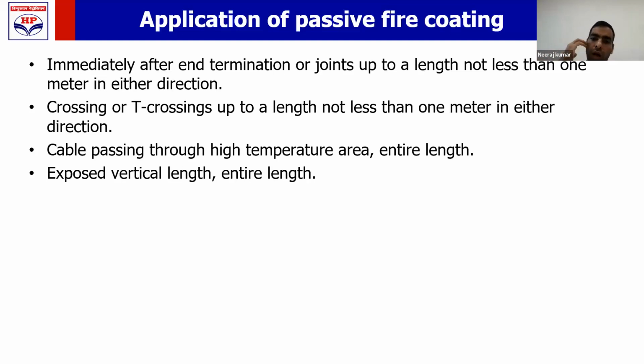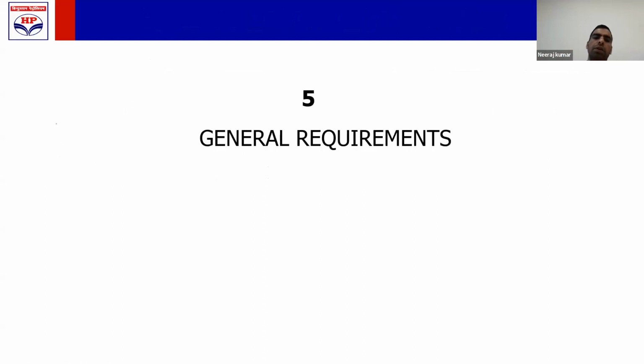If your cables are passing through a high temperature area, some steam line is going and your cable is passing along that steam line, then your cable should be provided with this fire retardant coating. A special attention should be given to vertical length. If you are taking a cable in a multi-story building, then either cable will pass through a vertical trench kind of thing. Then the entire length of the cable should be provided with this fire retardant coating, because the fire spreads quite rapidly in the vertical length compared to the horizontal lengths. And this completes the fire prevention and control requirement for the cables.